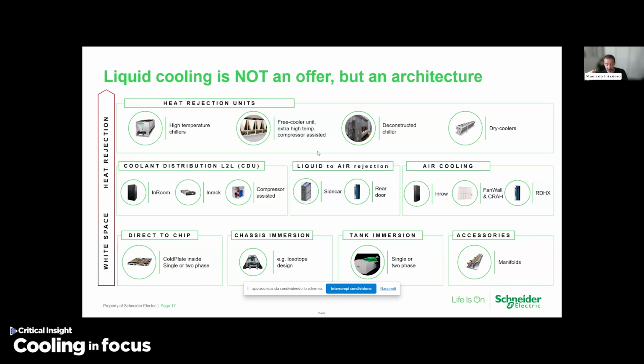For example, in a hybrid data center, it's very good to have cold plates connected to an in-room cooling distribution unit, with some complementary air cooling to dissipate the electrical portion, all connected to a heat rejection unit. Which one? A dry cooler can be used, certainly it is possible, but only for low density and low climatic conditions. For hot, warm zones or high density, a dry cooler is not enough.